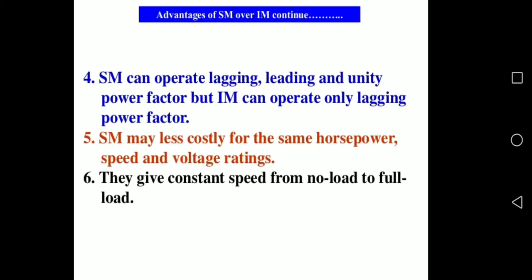A synchronous machine can operate at lagging, leading and unity power factor conditions, but an induction machine can only operate at lagging power factors. Synchronous machines may be less costly for the same horsepower, speed and voltage rating. And a synchronous machine gives a constant speed from low to high loads, which is not possible with an induction machine.